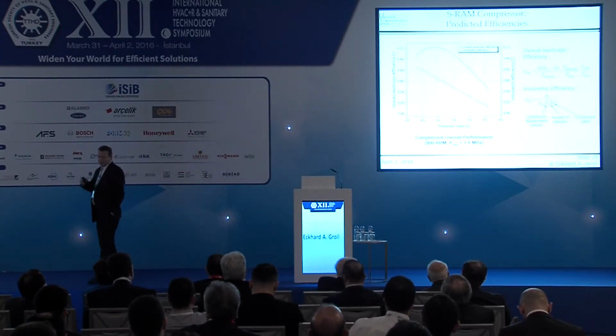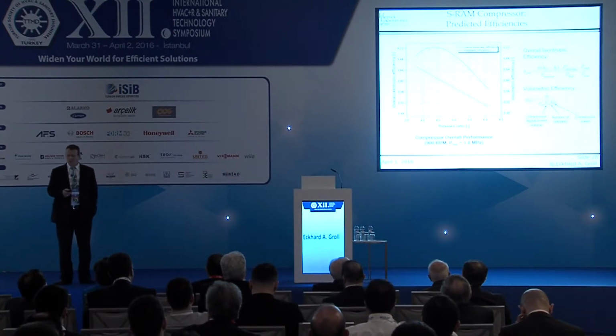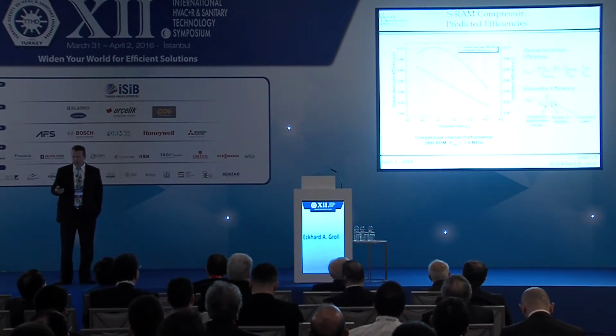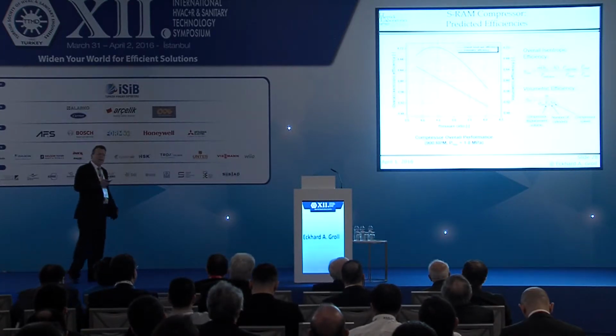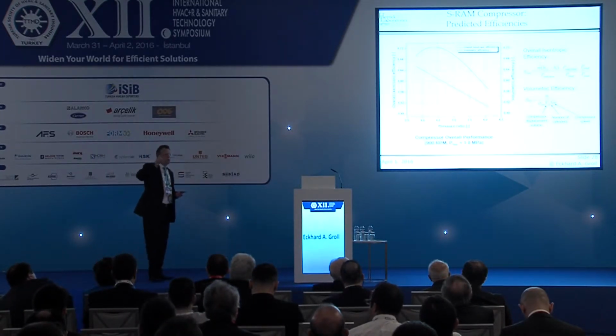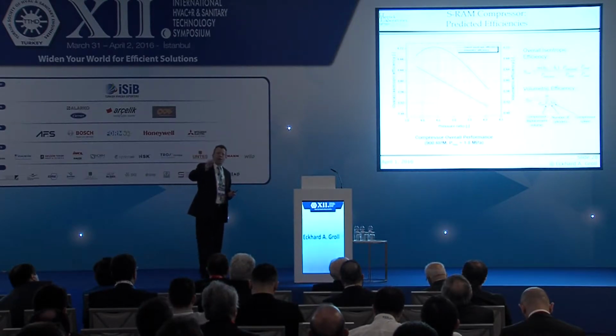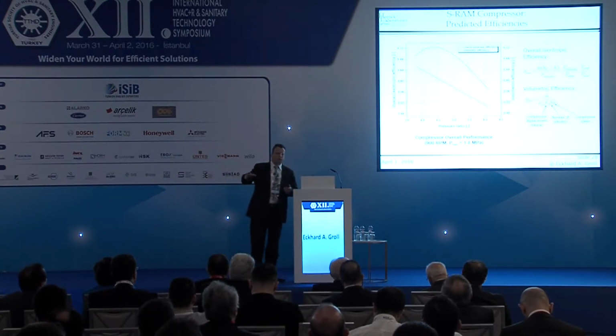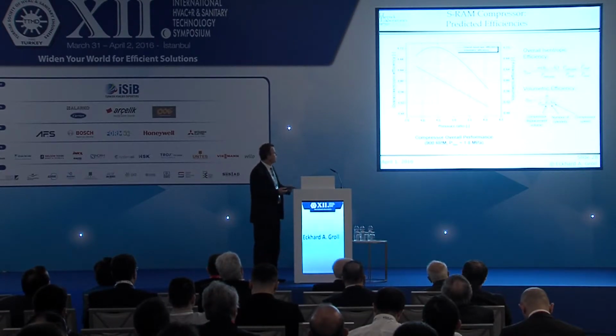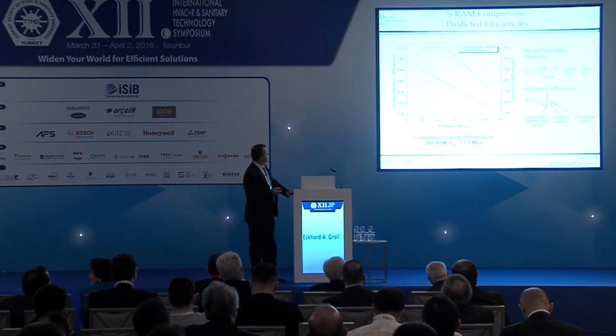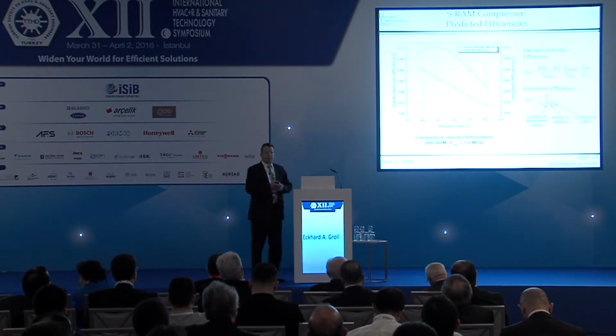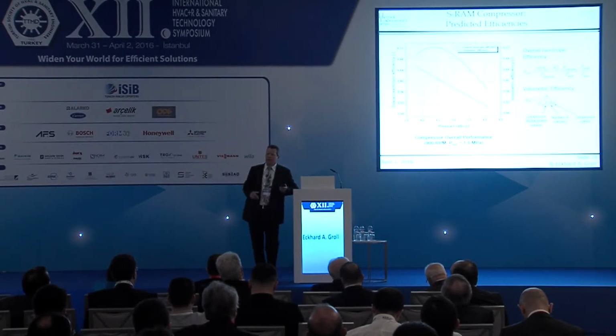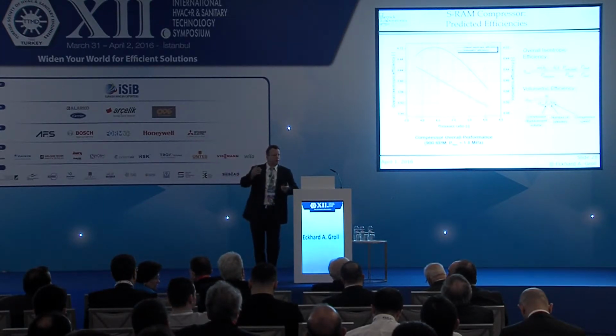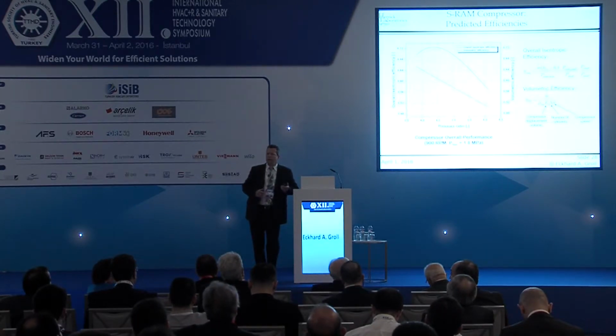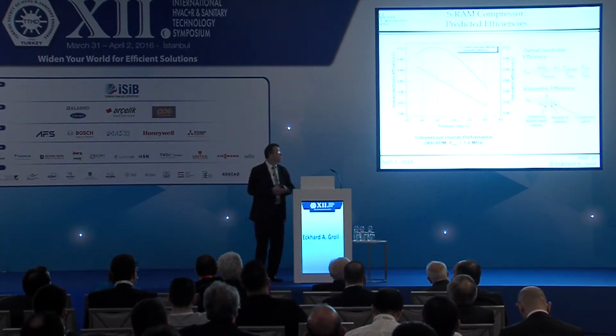But anyway, here we determined an overall isentropic efficiency that I mentioned. It's typically defined as the isentropic compression process over the electric power input, so we're taking everything into account. In this case, we achieved a maximum efficiency of 70% with our machine, which for a CO2 reciprocating type design, oil-free, is a great result for us. We're very satisfied with that.